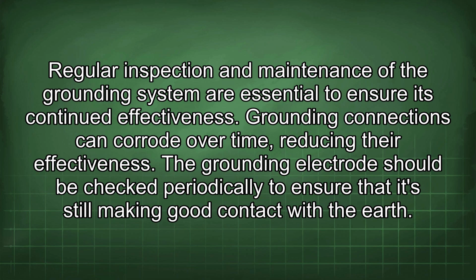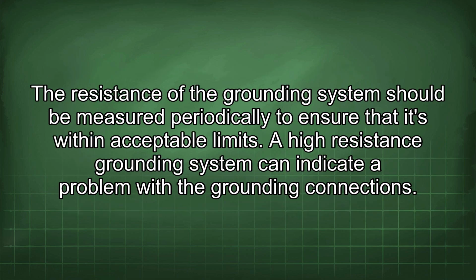Regular inspection and maintenance of the grounding system are essential to ensure its continued effectiveness. Grounding connections can corrode over time, reducing their effectiveness. The grounding electrode should be checked periodically to ensure that it's still making good contact with the earth. The resistance of the grounding system should be measured periodically to ensure that it's within acceptable limits. A high resistance grounding system can indicate a problem with the grounding connections.